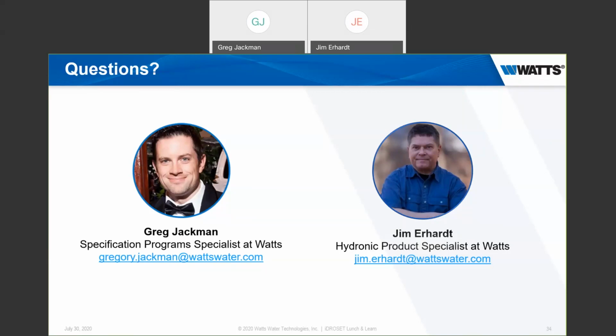Is the max flow in LPH or LPM? Max flow, you'll see in the spec sheet is rated in GPMs. So the 2-inch valve, for example, goes up to 44 GPM. So if I'm doing the math right in my head, that's 440,000 BTUs. The 1-inch valve, I'm just pulling the ones I remember, the top range is 7 GPM, so that's 70,000 BTUs. So that's how you would determine the correct valve for the application.